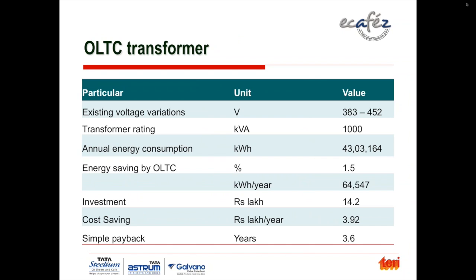So this is basically an on-load tap change transformer, which was recommended to the unit. One of the reasons for having it was the voltage variation. There was substantial voltage variation: you can see 383 volts, and it went up to 452 volts. Essentially, at night the voltage will be very high, typical of many industrial areas within India, whereas you require 415 volts. So there is huge voltage variation in the input.